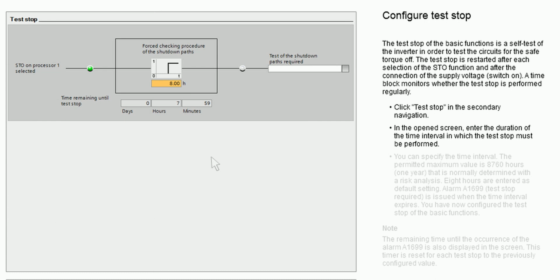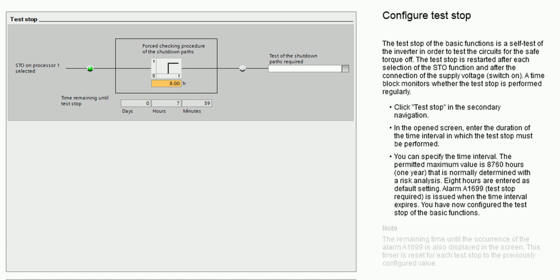In the open screen, enter the duration of the time interval in which the test stop must be performed. You can specify the time interval. The permitted maximum value is 8,760 hours, 1 year, that is normally determined with a risk analysis. 8 hours are entered as default setting. Alarm A1699, test stop required, is issued when the time interval expires. You have now configured the test stop of the basic functions.